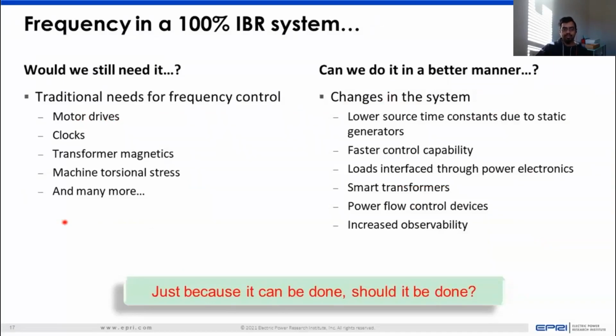It helps to think about these scenarios: traditional needs of frequency control stem from things like motor drives, but motor drives are transitioning to power electronics. We have clocks that may run on the system frequency, magnetics, and machine torsional stress. If you have a 90% or 80% inverter-based resource system, there can be torsional stress on machines.